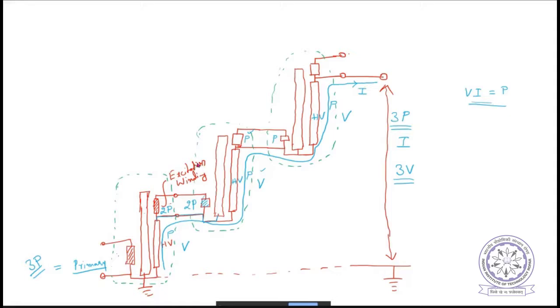After detailed investigations, it was found that the reactance of these transformers comes in series with the capacitance of the load. Load in high voltage is almost only capacitance, right? So that capacitance comes in series with the reactance of these transformers and causes a resonance.